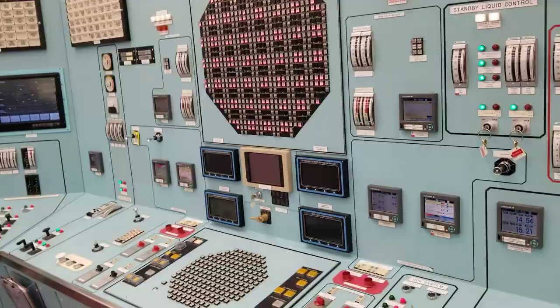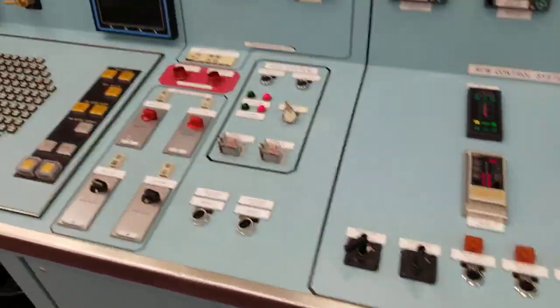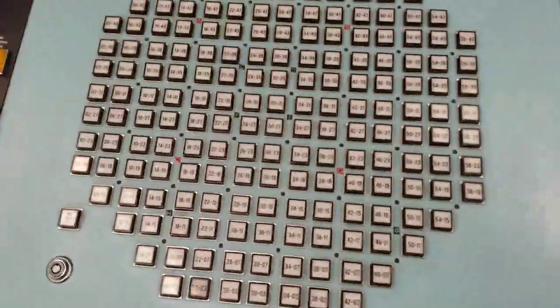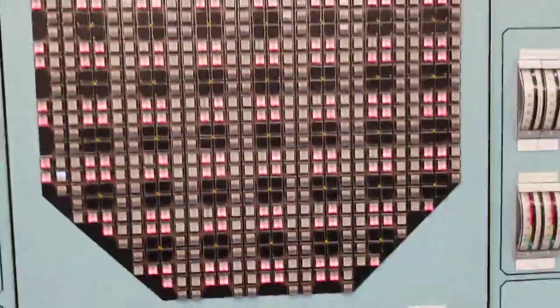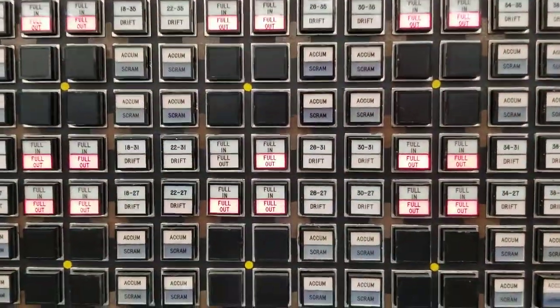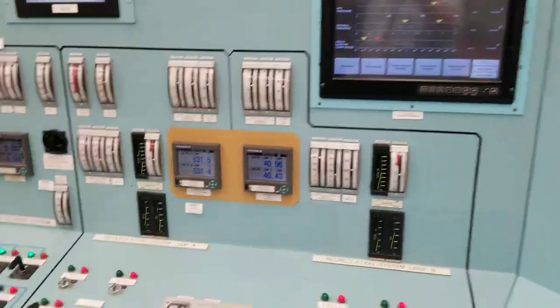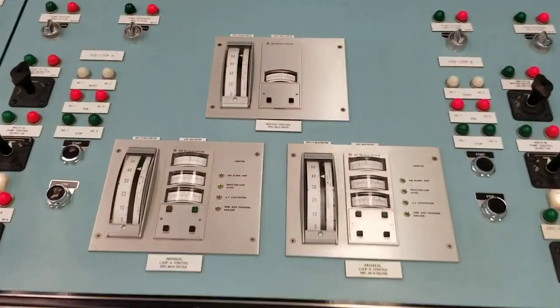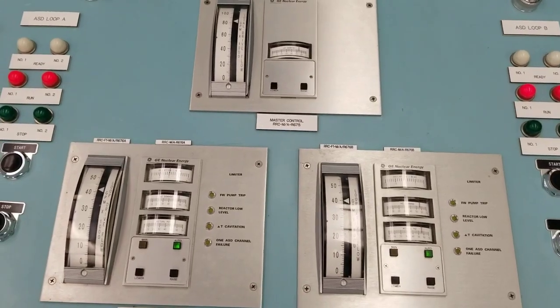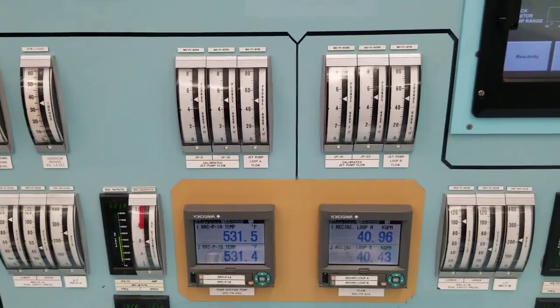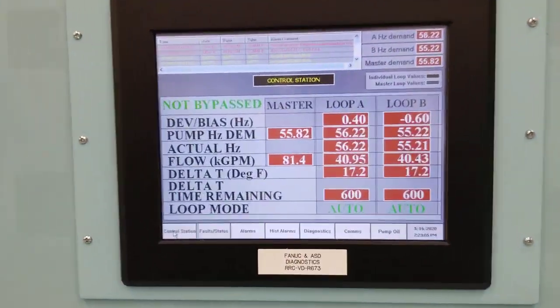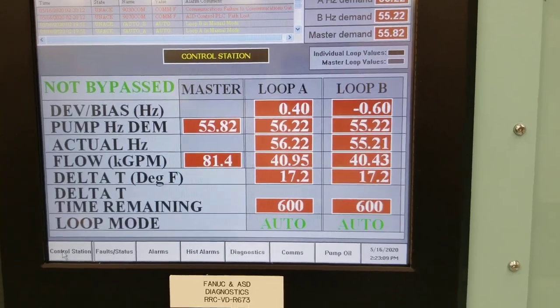And then this is the panel where the reactor magic happens. We've got how we select all our control rods, and this is our full core display that shows the status of the rods — whether they're full in or full out — and if any problems happen, it shows up there. This is our recirc system. Our recirc pumps provide flow through the core, and these recirc pumps are what allow us to get more megawatts out of the reactor, because if our recirc flow goes down or you have natural circulation, then you're not able to remove as much heat.